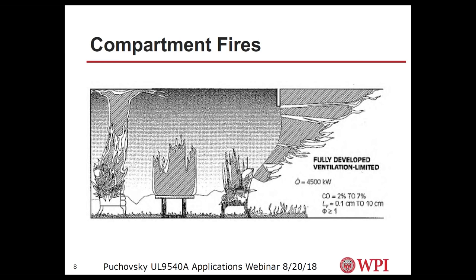Next slide, please. And again, if there is sufficient oxygen within the room, at some point you will reach this point of flashover. And this point of flashover is essentially where every burning surface in that room is involved in flaming combustion and it's burning. And again, this is the point where it becomes, I would say, very critical from a structural standpoint within the building to be able to withstand this. Now we're also driving the fire as this engine that'll produce these effects of heat and toxic products and smoke that can be driven through the building because of the energy through that combustion process.